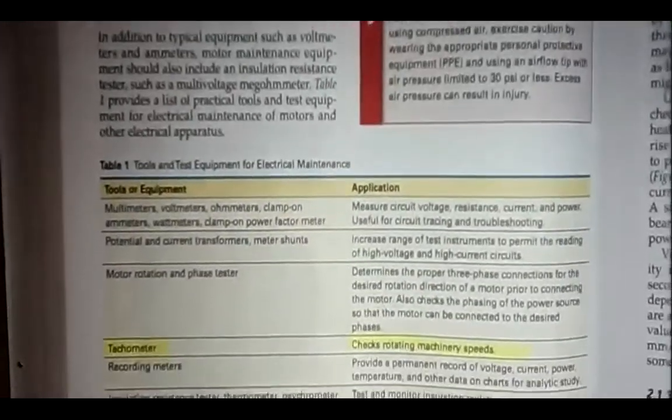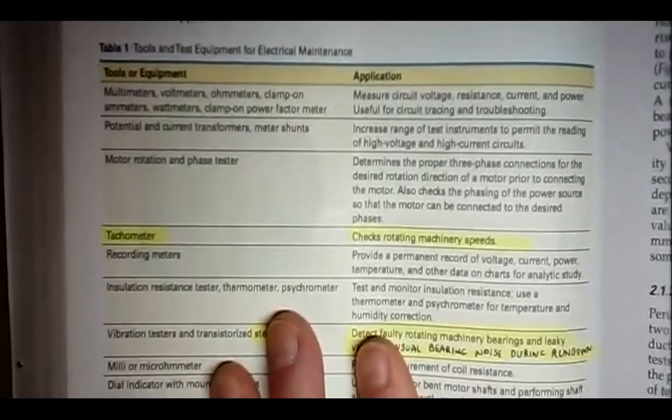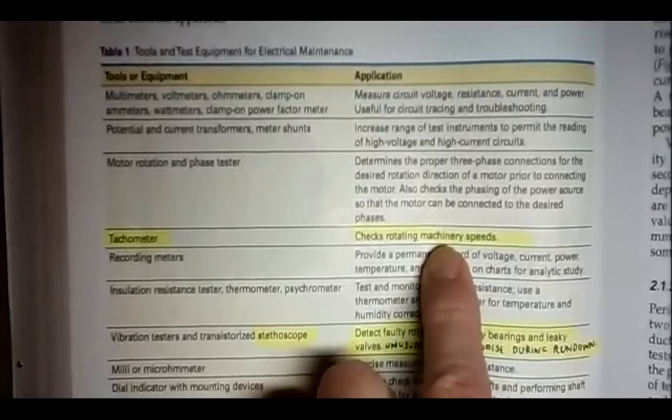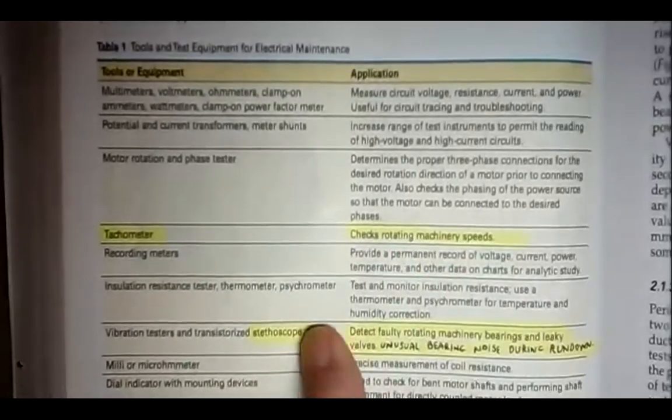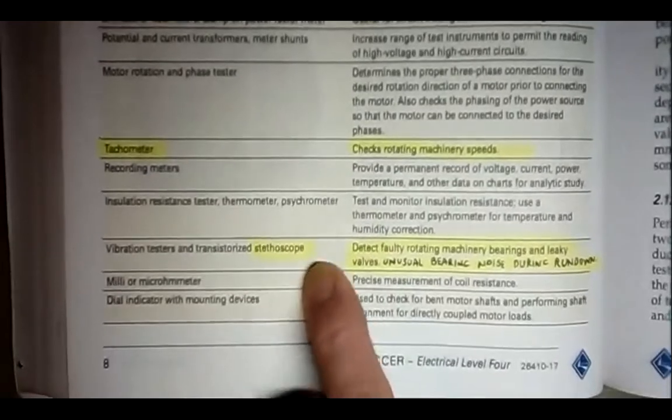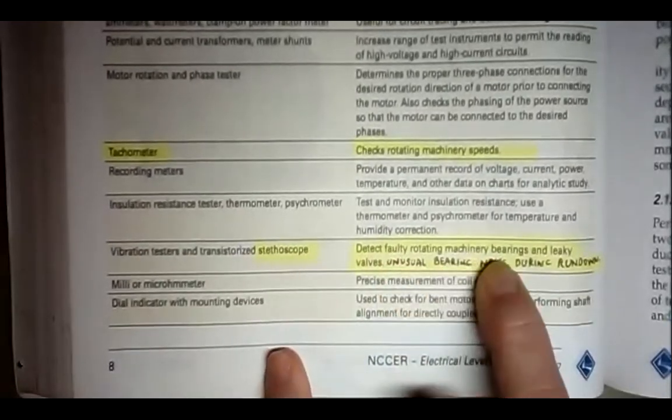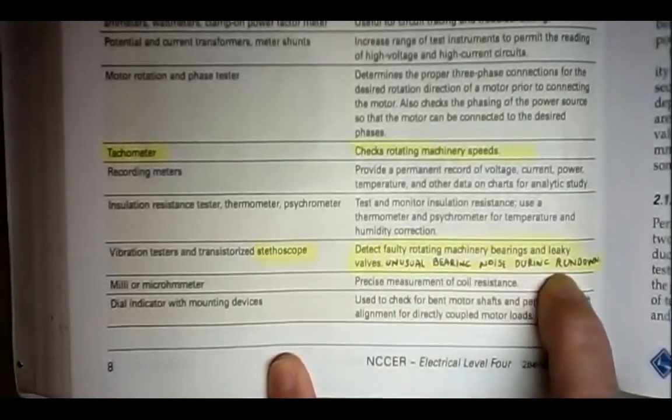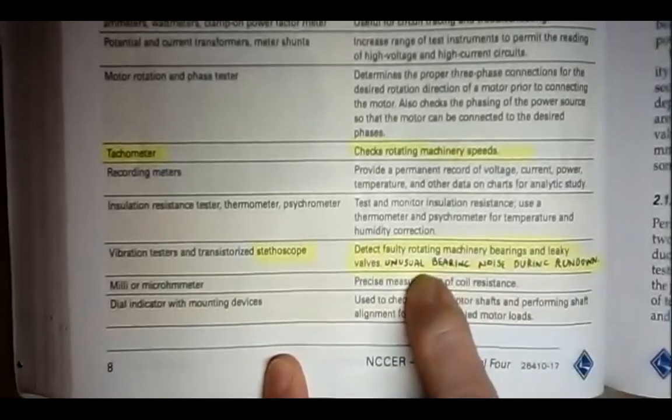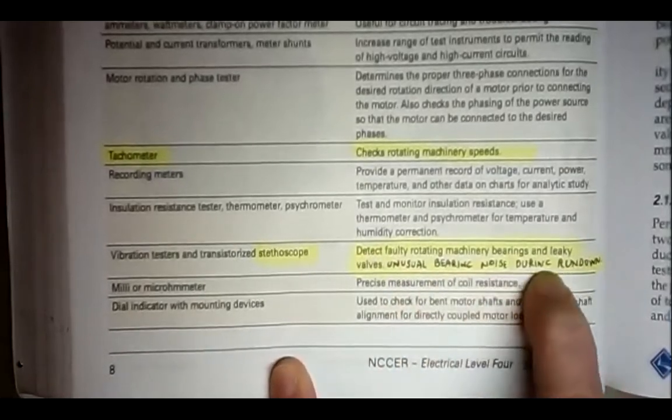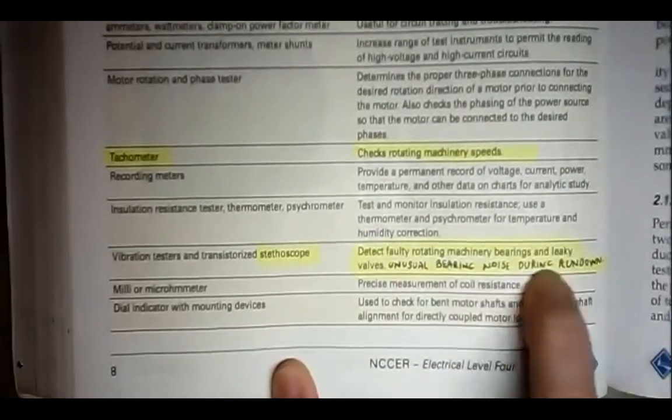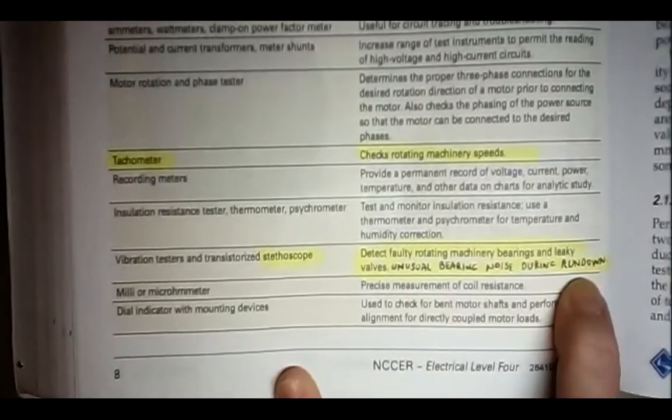On the bottom of page eight, it says tools and test equipment for electrical maintenance. You can use a tachometer. Check the rotating speed of the motor. Make sure that it's within specs. You can use a stethoscope. It detects faulty rotating machinery bearings and leaky valves. If there's unusual bearing noise during rundown, like you run the motor and then you turn the motor off and it's running down, you can listen to it. And if the bearings have a lot of slip in them, a lot of play, you'll hear a lot of chatter, a lot of noise going on in there while the motor is actually slowing down.